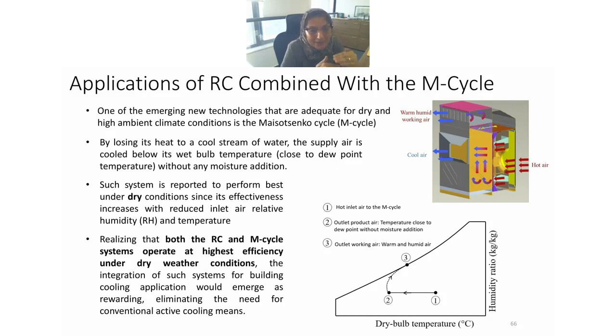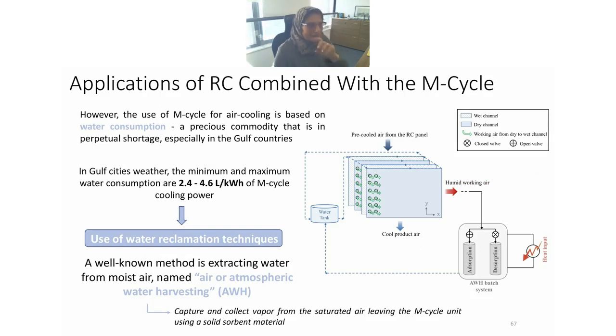The ambient air goes in the dry channel, and another stream of air goes in the wet channel. While the water is evaporating, it cools the air, and the air in the dry channel is sensibly cooled. With proper design, it could reach the dew point, and that's why we're going to combine it with the RC panel.